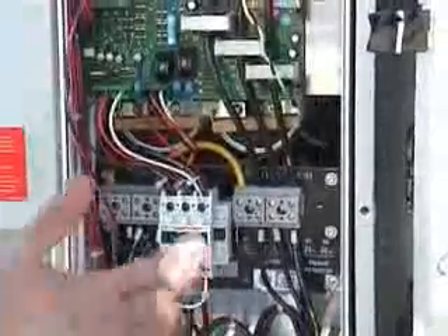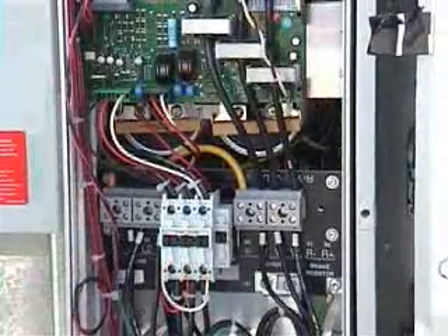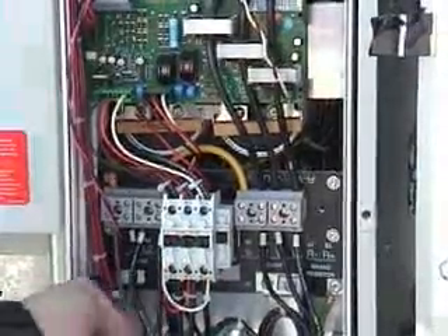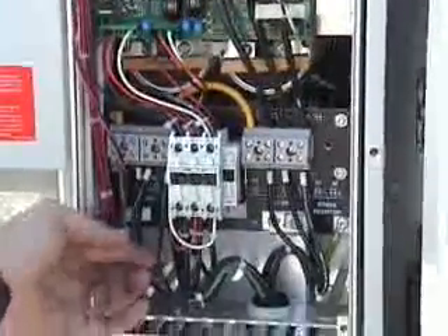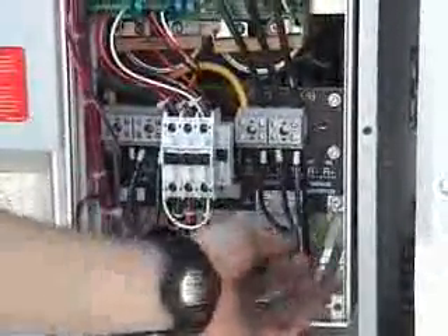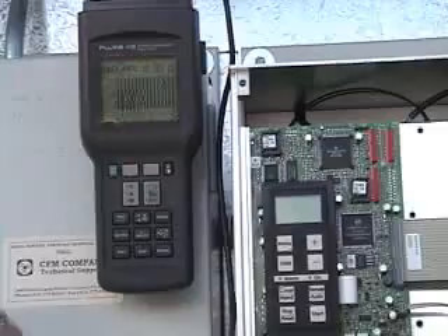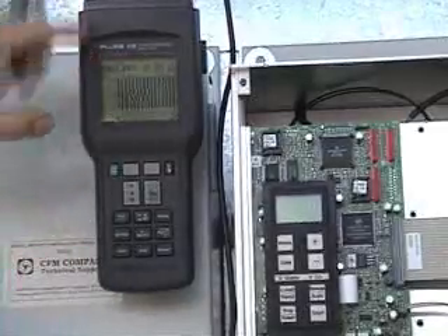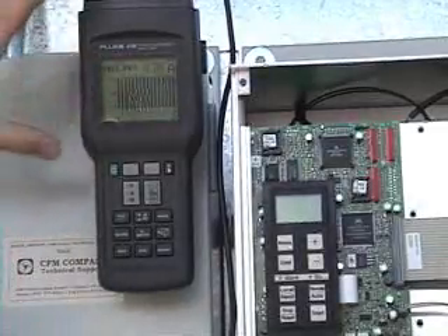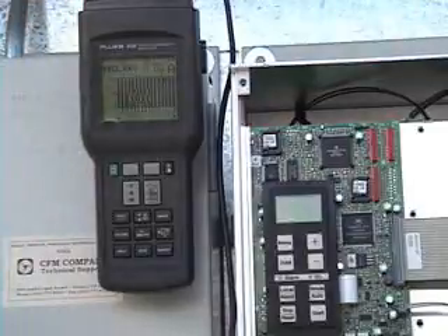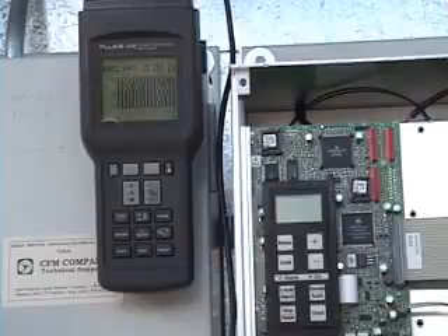So what we want to look at today with the frequency analyzer is the frequency of the current as it's going into the frequency drive, and then we'll look at it as it's coming back out of the frequency drive right here. Okay, this is a Fluke 41B. It's a power harmonics analyzer. We use this to analyze the frequency that the frequency drive is putting out to the motor, and we're trying to test to make sure that the total harmonic distortion out of this meter is less than about 5%.